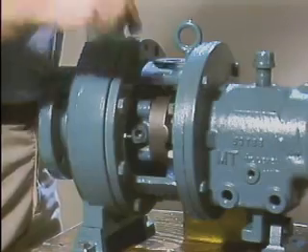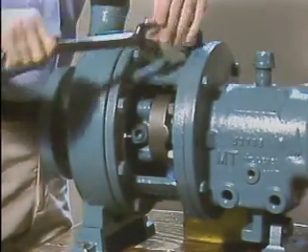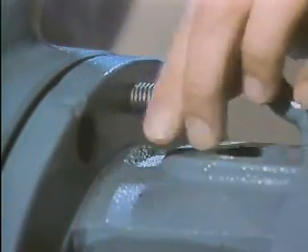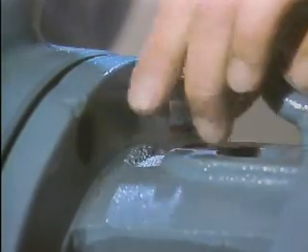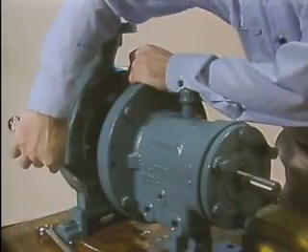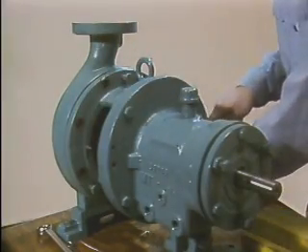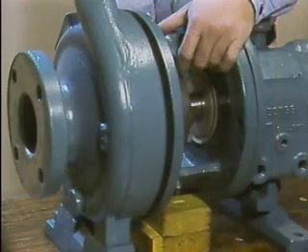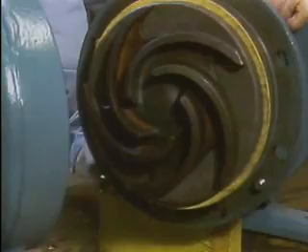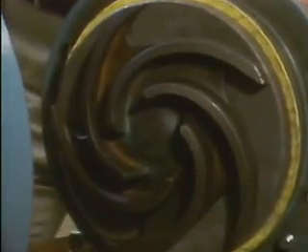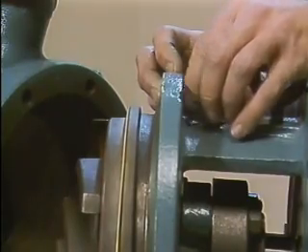One of the first steps is separating the casing from the pump frame. To do this, the casing bolts must be removed. Then jacking bolts are installed to force the casing and pump frame apart. The jacking bolts are turned in a crosswise pattern to evenly dislodge the casing from the frame. Now the frame and the bearing housing can be moved to the side to allow for easy access to the remaining parts. The jacking bolts are also removed.